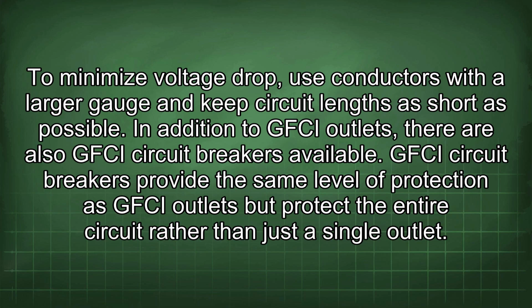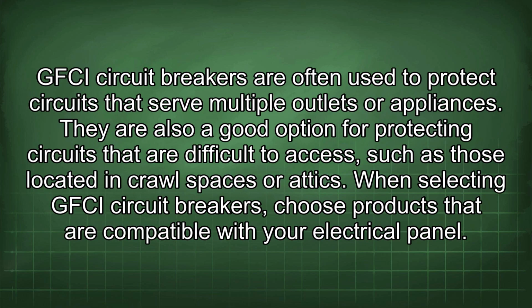In addition to GFCI outlets, there are also GFCI circuit breakers available. GFCI circuit breakers provide the same level of protection as GFCI outlets but protect the entire circuit rather than just a single outlet. GFCI circuit breakers are often used to protect circuits that serve multiple outlets or appliances. They are also a good option for protecting circuits that are difficult to access, such as those located in crawl spaces or attics. When selecting GFCI circuit breakers, choose products that are compatible with your electrical panel.